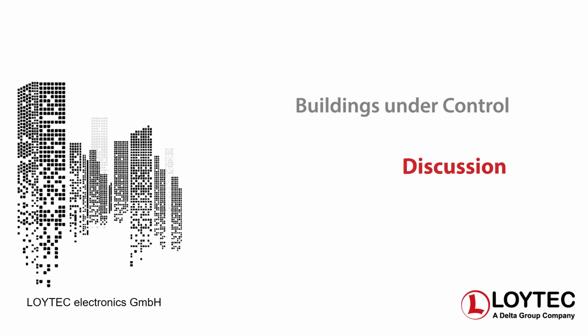Or maybe for some reason you have to exchange the device, or you start a new project, or something happens and you lose your old trend data, then you need to start right from the beginning. But in the new firmware version, I think we put it in 7.6 firmware, you now can enter these values manually, so that you can initialize the values on the web interface, and these values are then used to calculate all these recordings and data. That's quite a new feature, actually.